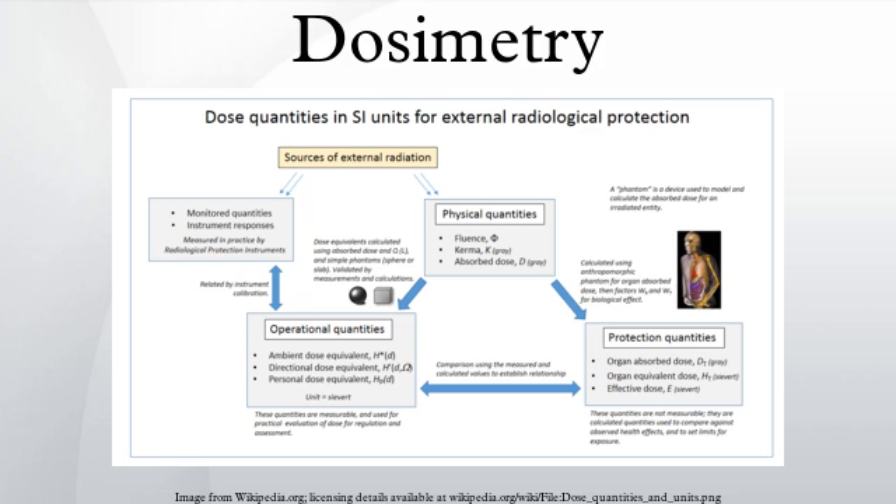Because the human body is approximately 70% water and has an overall density close to 1 g per cm³, dose measurement is usually calculated and calibrated as dose to water. National standards laboratories such as the NPL provide calibration factors for ionization chambers and other measurement devices to convert from the instrument's readout to absorbed dose. The standards laboratories operate a primary standard, which is normally calibrated by absolute calorimetry, the warming of substances when they absorb energy. A user sends their secondary standard to the laboratory, where it is exposed to a known amount of radiation and a factor is issued to convert the instrument's reading to that dose. The user may then use their secondary standard to derive calibration factors for other instruments they use, which then become tertiary standards, or field instruments.